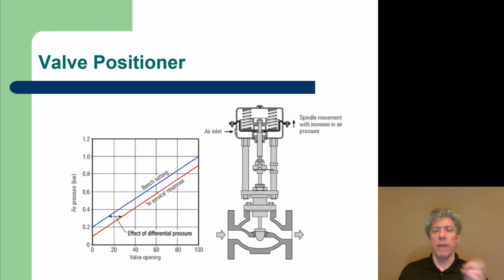This is a huge difference in the amount of flow that's expected. Another thing to consider is what's called valve authority. There's a mistake that I hope you won't make. I'm going to tell you about it now. There was a time I saw a system, and there were some engineers in the company I was working for that were working on this valve, and they were having a lot of trouble with it because they had 1-inch piping and they had selected a 1-inch valve to go with it. Just the so-called line size of the valve. What that means is they just chose a valve that had threaded connections the same size as the piping. They put it in and they were having trouble with it because it turned out that for the valve to restrict flow at all, the valve had to almost completely shut off the flow. So it was almost at the limit of its travel. And the problem with that is that the flow was very sensitive to any motion in the valve stem. And so what would happen is the valve, in trying to control and modulate the flow, would make a small change, and that would make a drastic change in the flow rate through the valve. See, valves have to have what's called valve authority. They have to be one of the main restrictions in the flow piping.